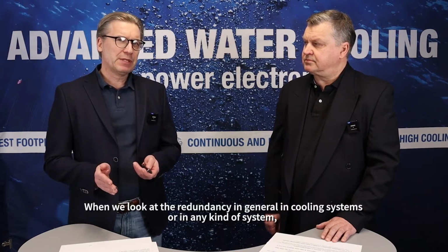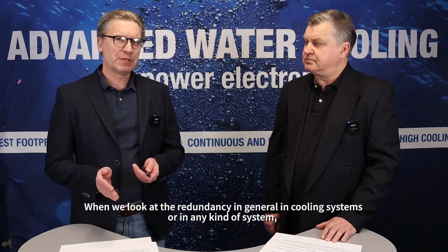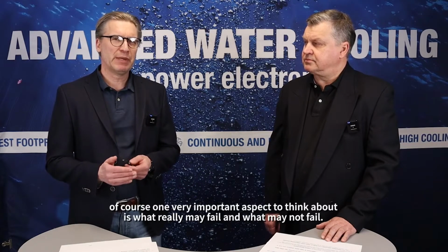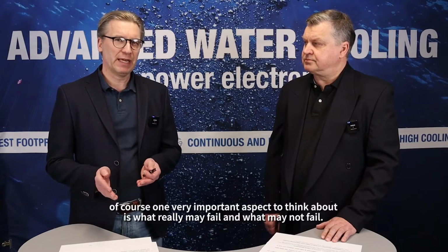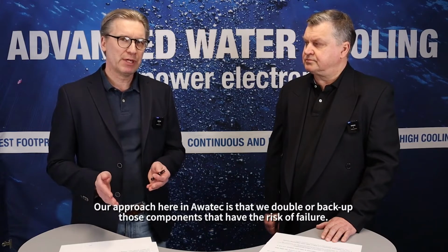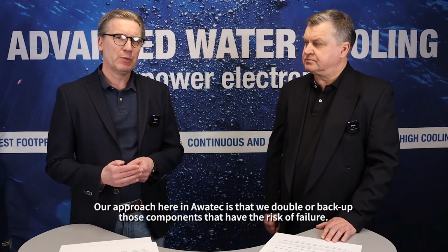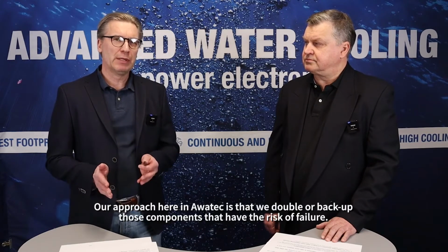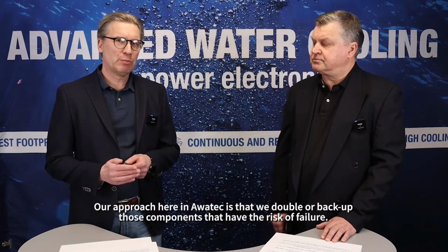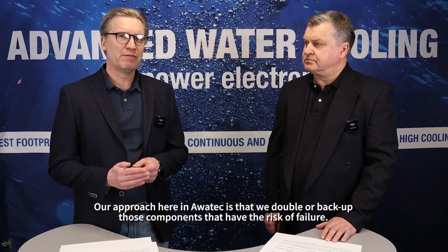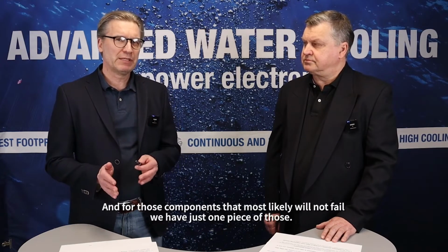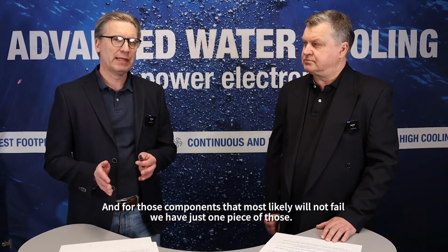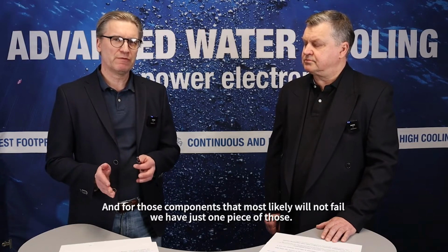When we look at the redundancy in general in cooling systems or in any kind of system, of course one very important aspect to think about is what really may fail and what may not fail. So our approach here in Adwatec is that we double or back up those components that have the risk of failure, and for those components that most likely will not fail, we have just one piece of those.